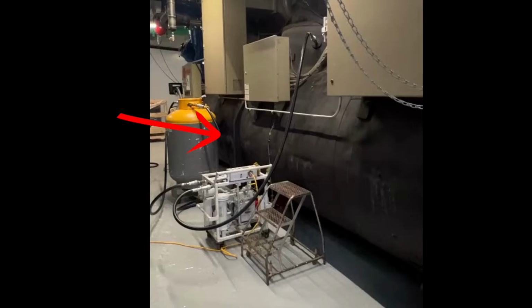This is my actual preferred method that I use myself all the time. I'm actually watching my hose, and I can tell based off how the hose is acting. Now, once the hose goes still, and you don't see it dancing around, and you don't feel it anymore, that is an indication that you now just have vapor refrigerant flowing through there. You no longer have a heavy liquid making the hose dance. It's just vapor. So that's another way of determining if you've gotten the liquid out and you're going to a vapor.